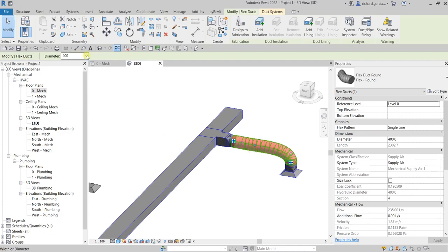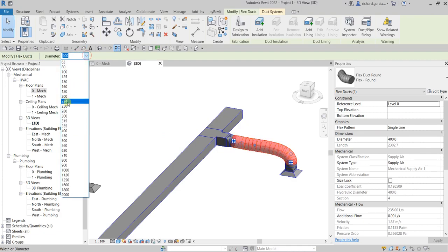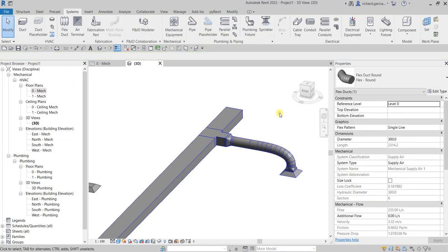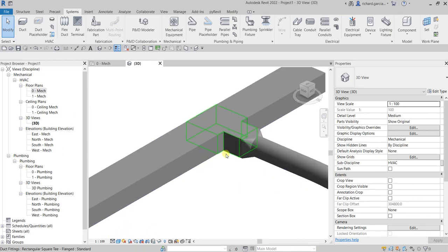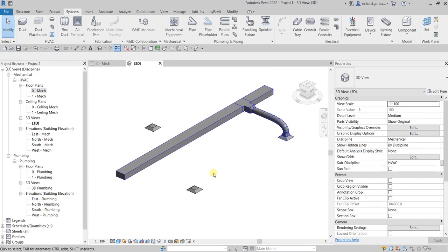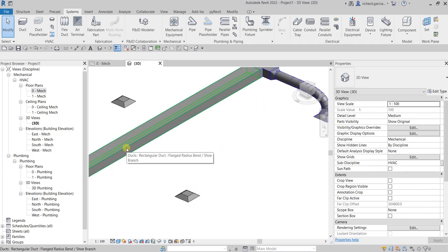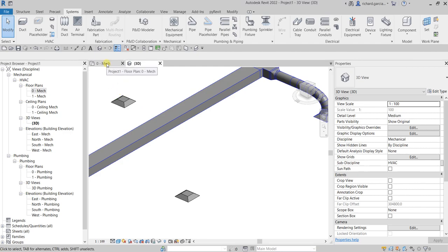If we check that out in 3D view, this is how it looks. Let me just change the size of my duct there to 300. So that's a T-junction type. Now let's say for this air terminal you want it to connect to your duct but the junction type should be a tap connection instead.